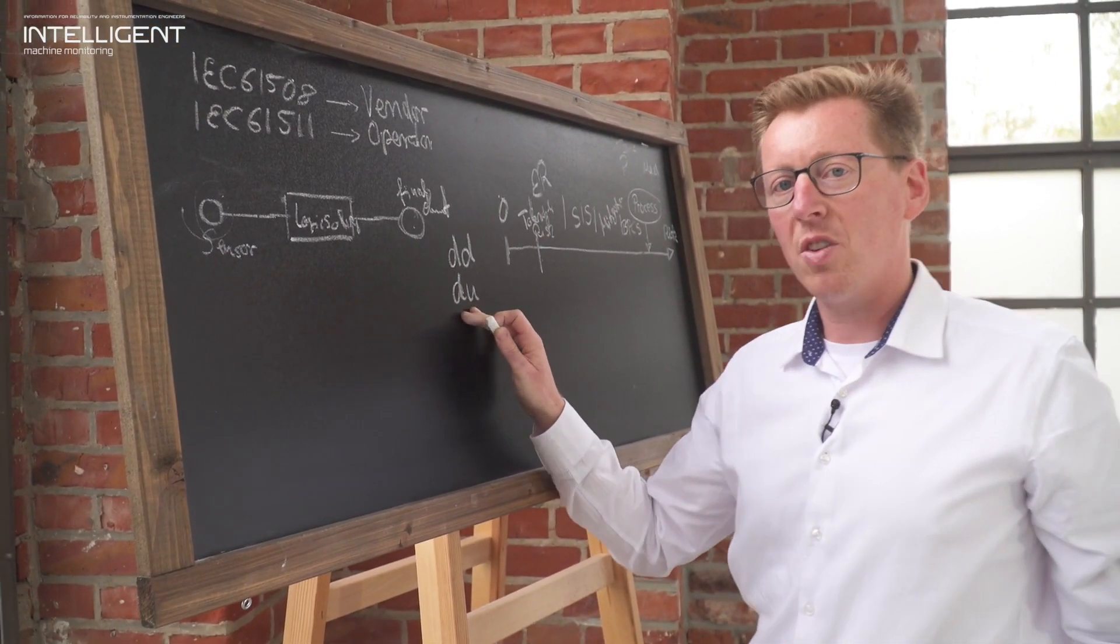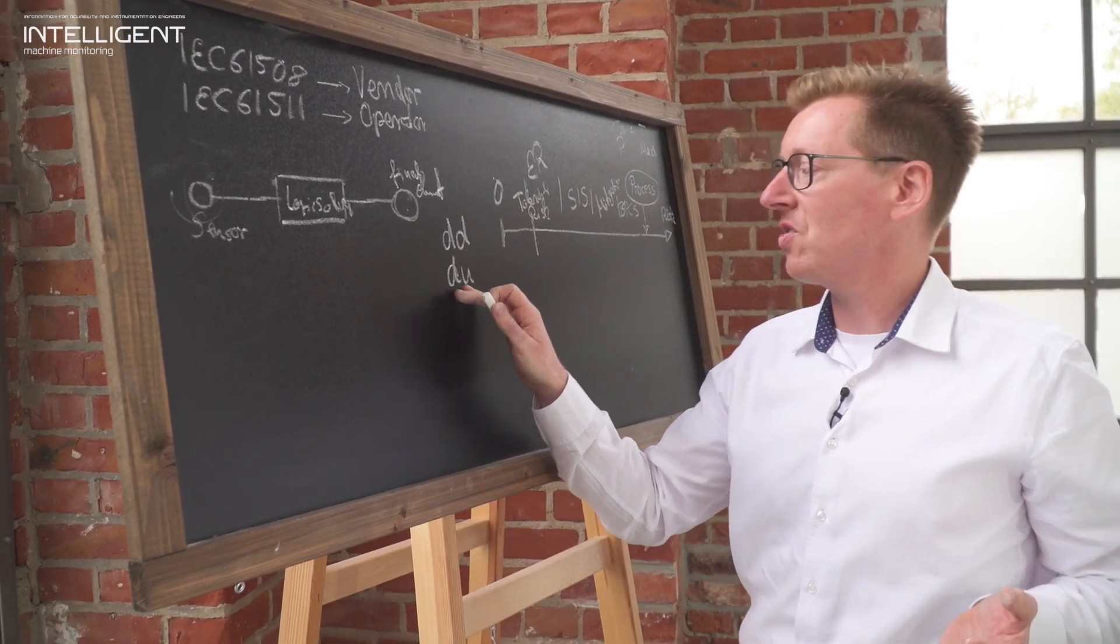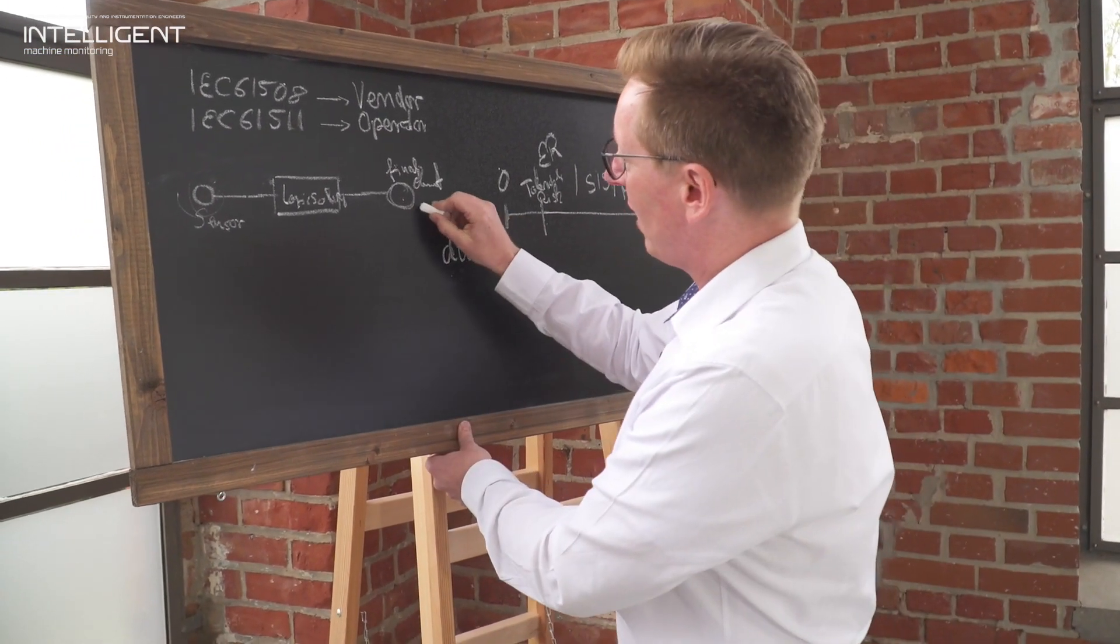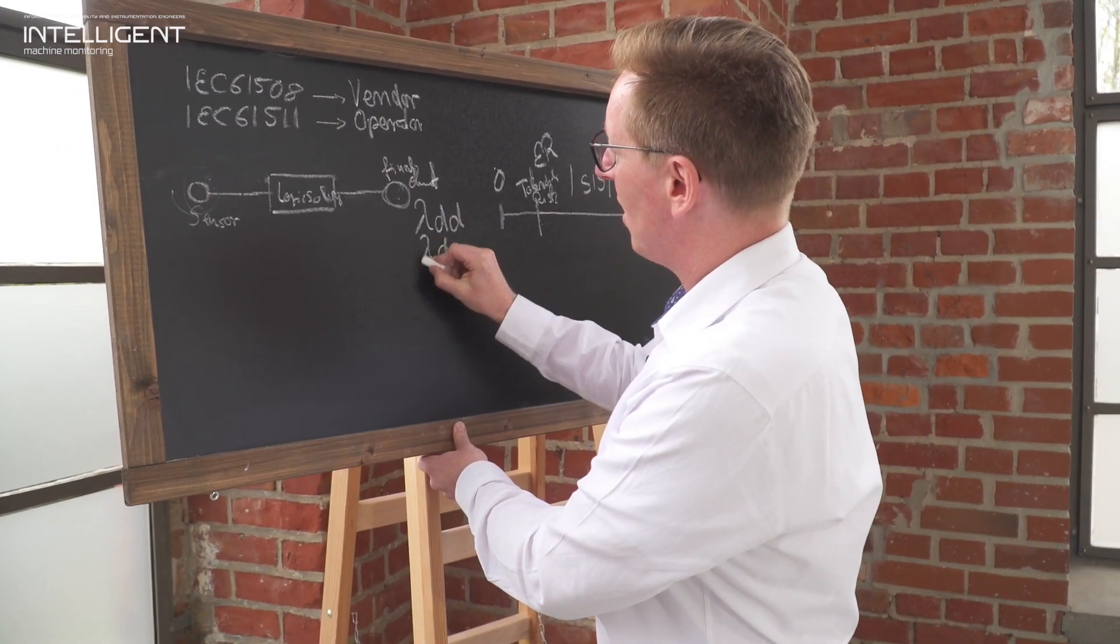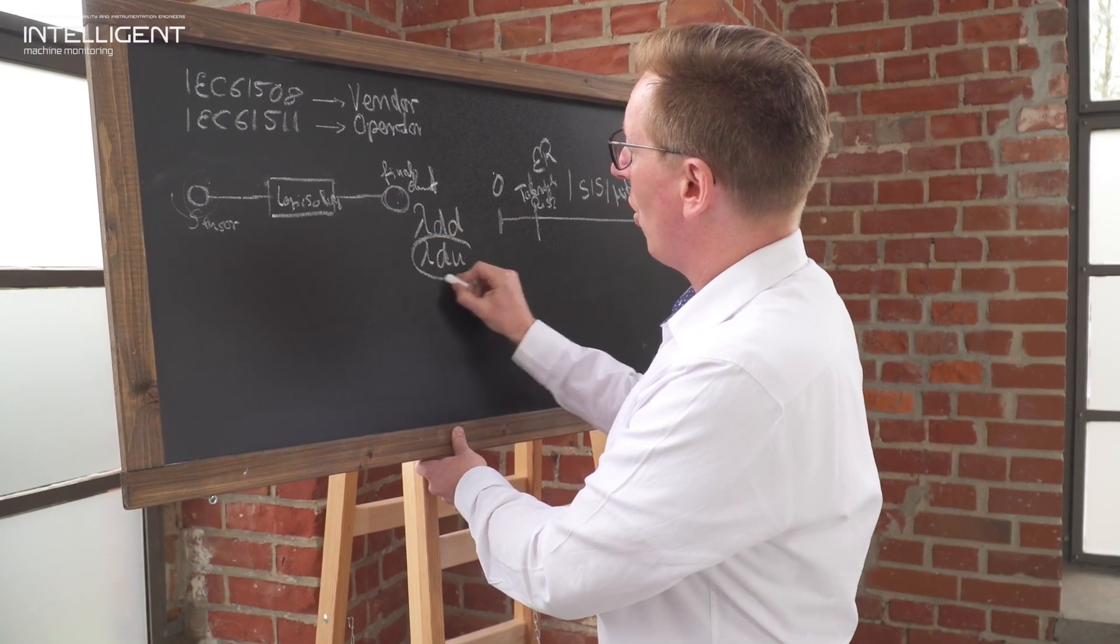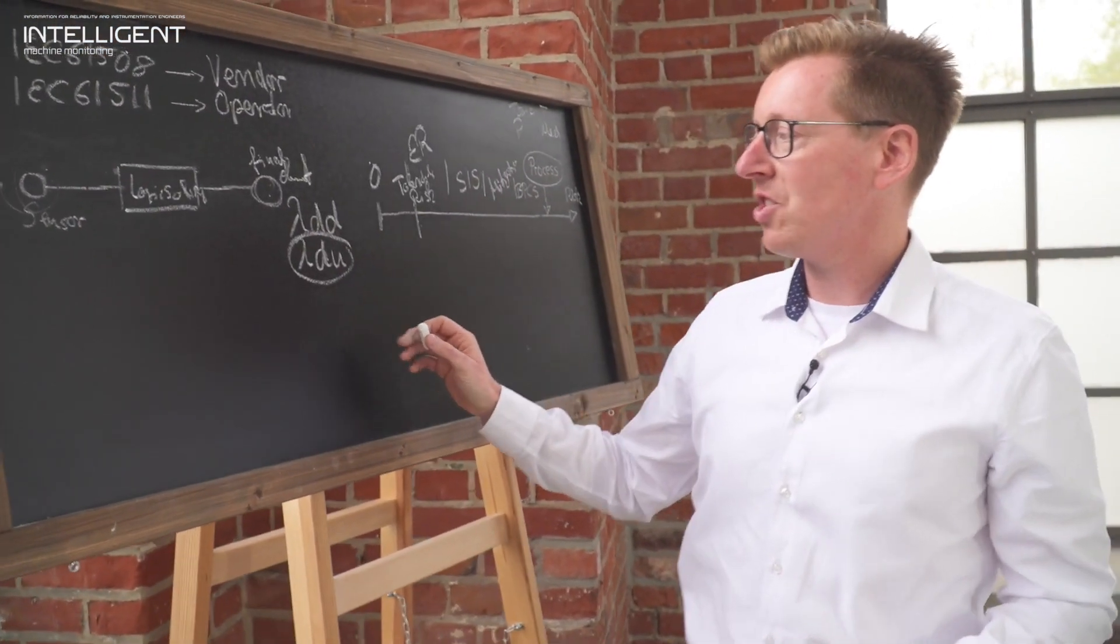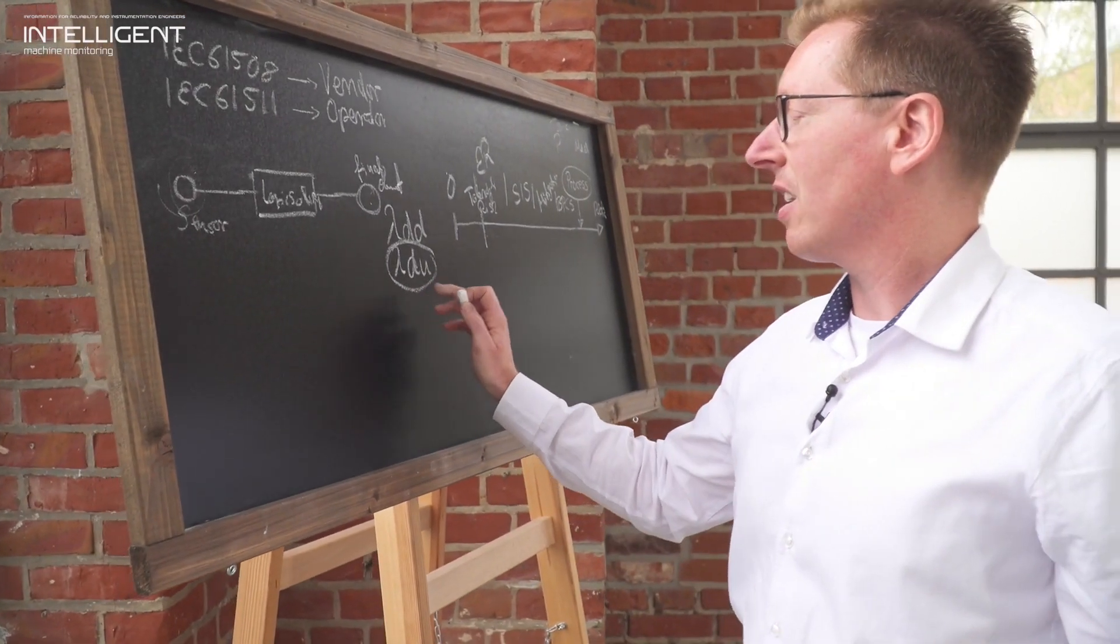But there is another problem and that is a dangerous and undetected failure mode. And those are the ones that really gonna bite you as an operator if these dangerous events remain undetected. There is the lambda DD and the lambda DU, and of all of these the lambda DU value is taken into consideration for the PFD calculation.